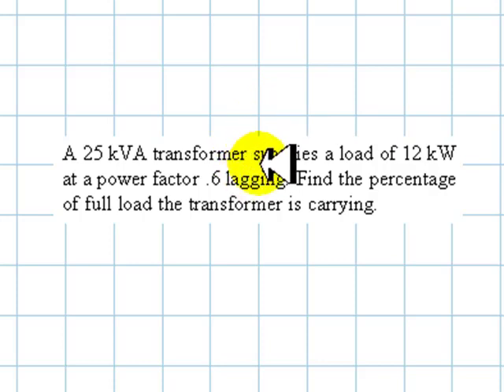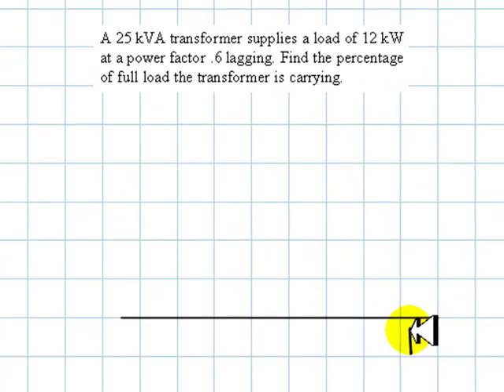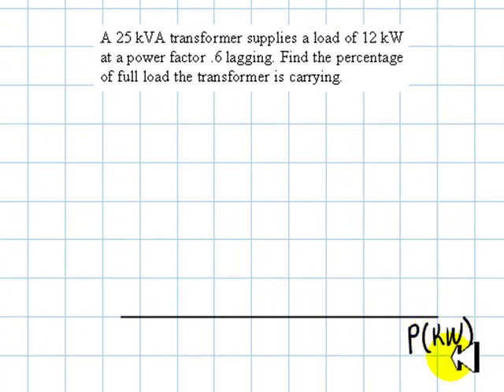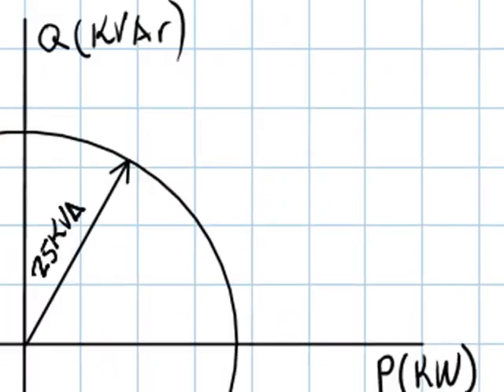Let's make a drawing on the complex plane of power, the one that has a real axis P in kilowatts, active power, and an imaginary axis Q, reactive power, in kilovolt-amperes reactive. What that means is that as long as the load of the transformer is within this circle of radius 25 kVA, the transformer is safe.